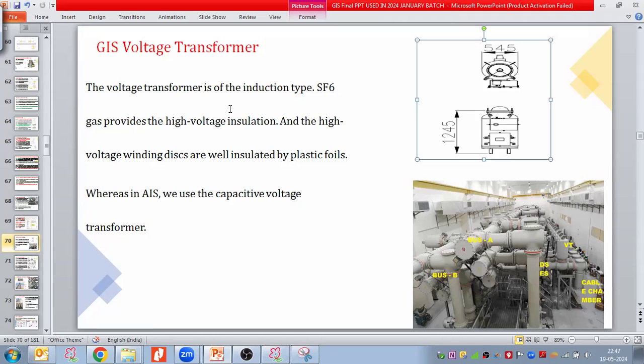So the VT is of the induction type. SF6 gas provides the high voltage insulation. Yesterday we discussed with one of the participants about the VT, and he said that we take the CVT in the case of GIS substations. Please note down, we take the CVT in the case of AIS, and if we require the CVT in the case of GIS, that would be an outdoor CVT, not an indoor CVT.